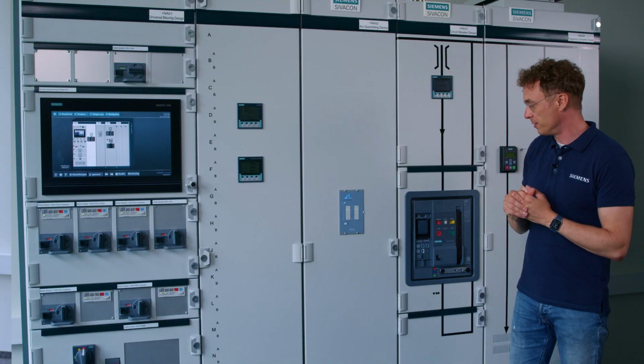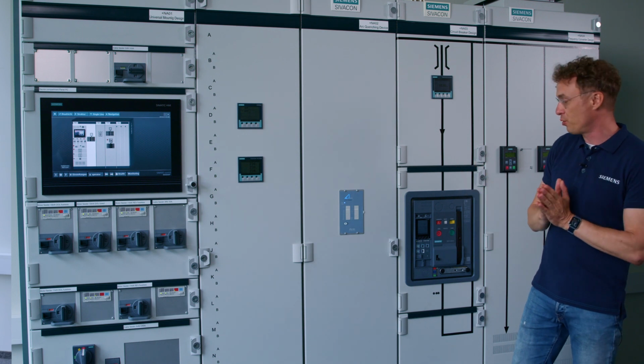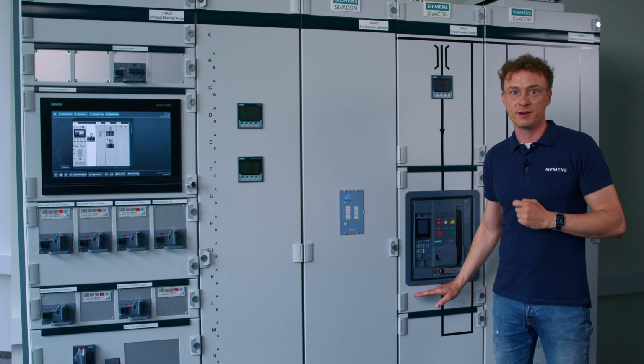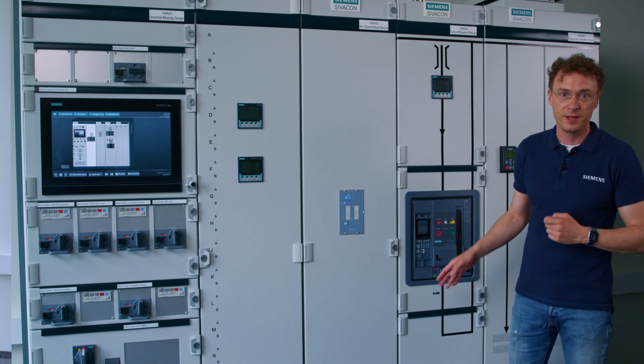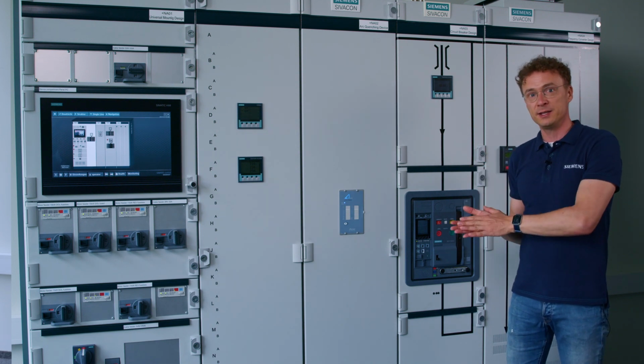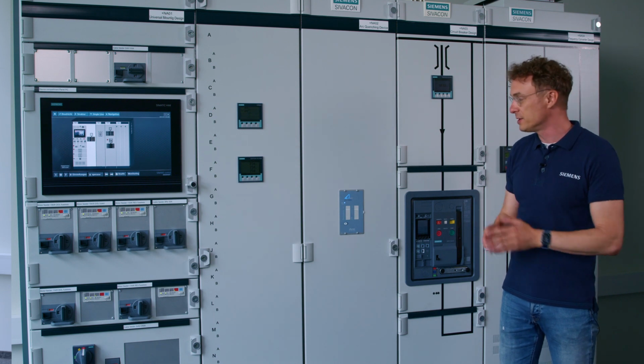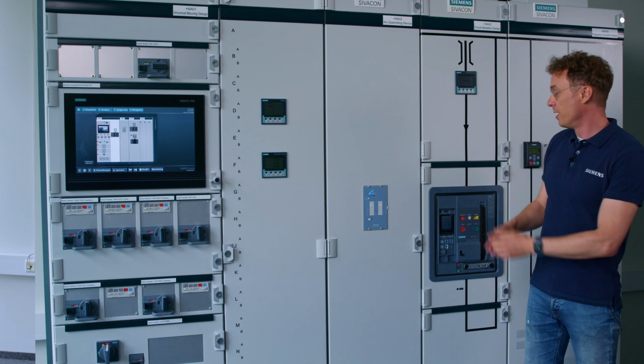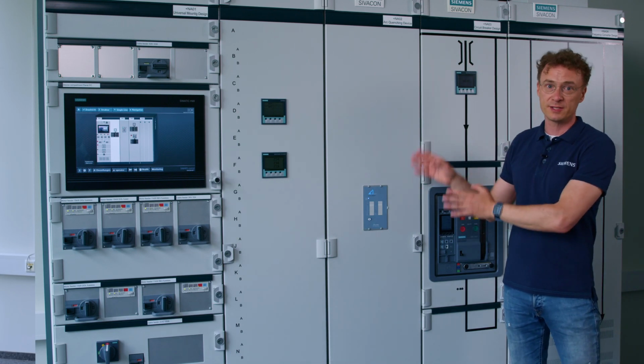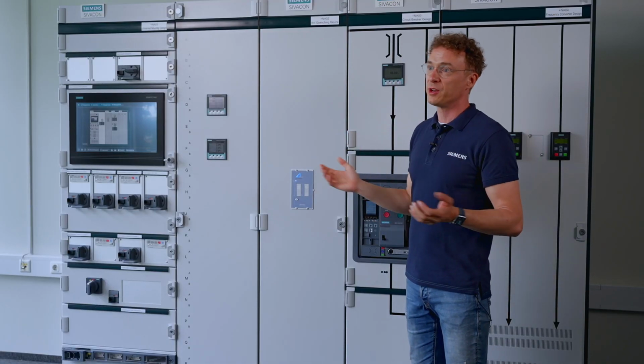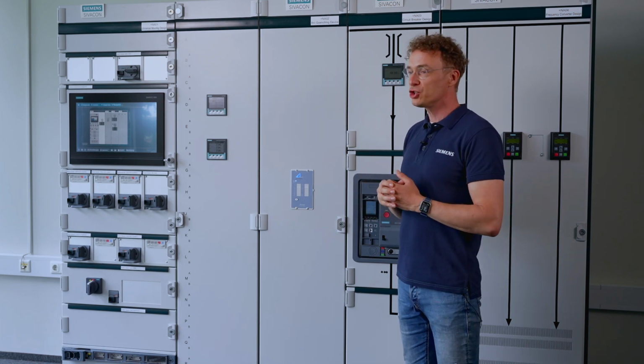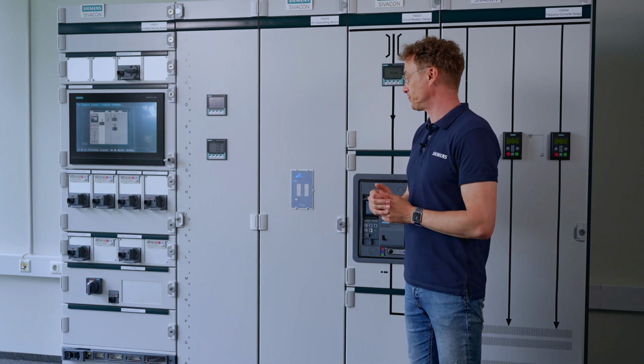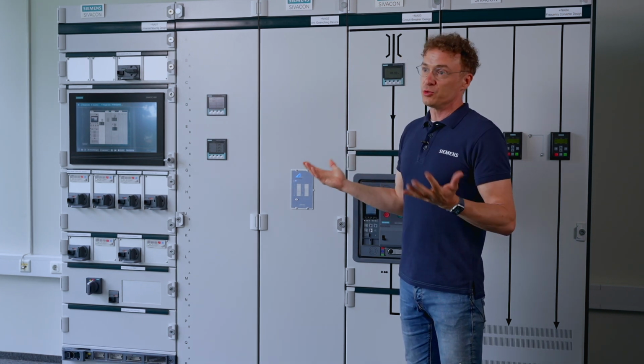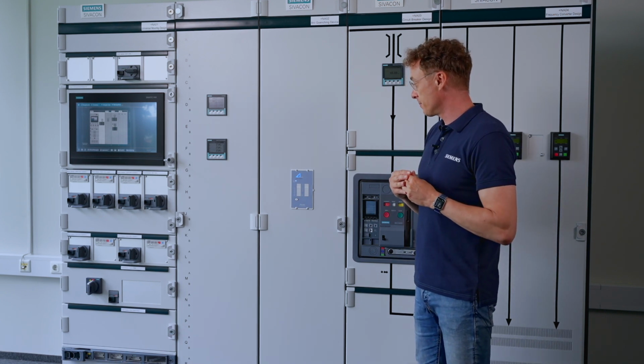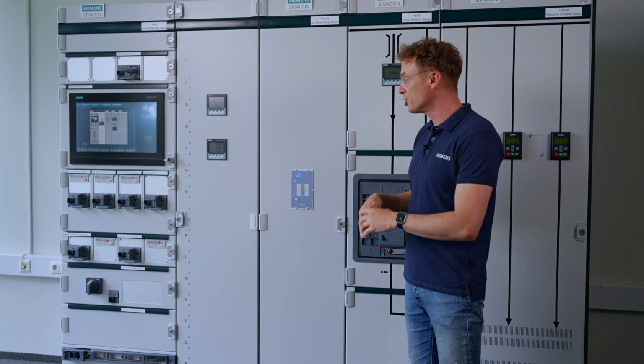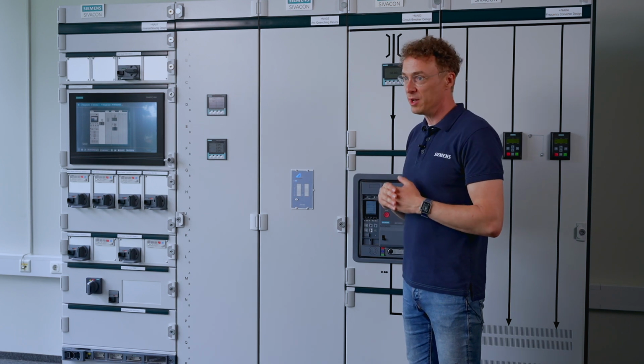To avoid false trippings, we combine this information with the current that is taken from the incomer. There are CTs in the incomer, and so if we see the light signal and on the other side we have the steep rising current, then this relay will send a trip signal at least to the breaker, but also very fast to the arc quenching device inside, which will then create a three-phase short circuit on the main busbar, taking away the energy from the arc flash, and extinguishing it that way. And it does that in a very fast time, so the energy that is released inside the switchboard is reduced to a minimum level.